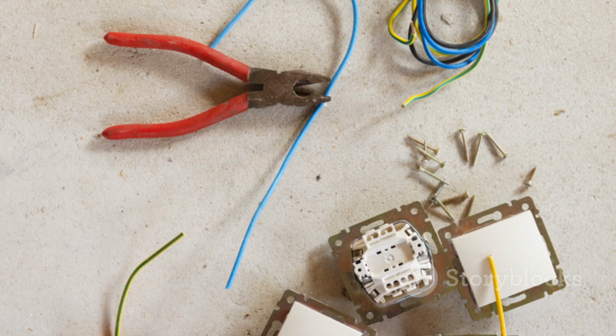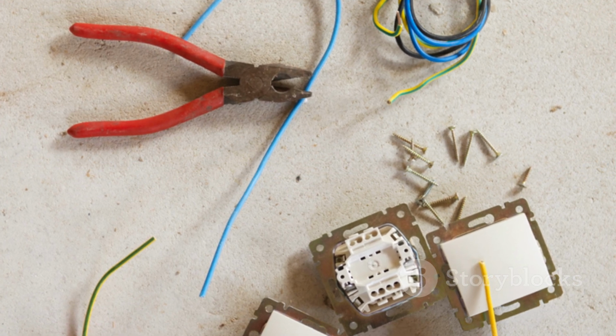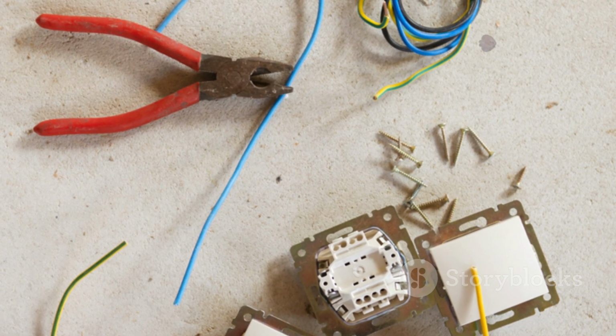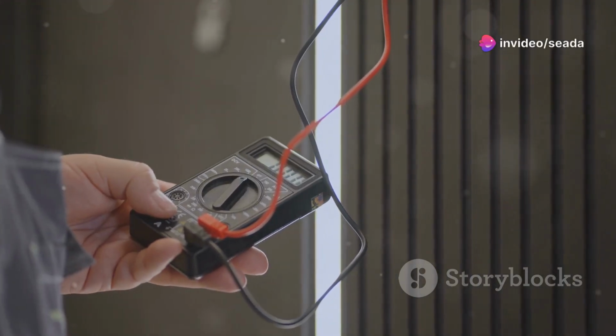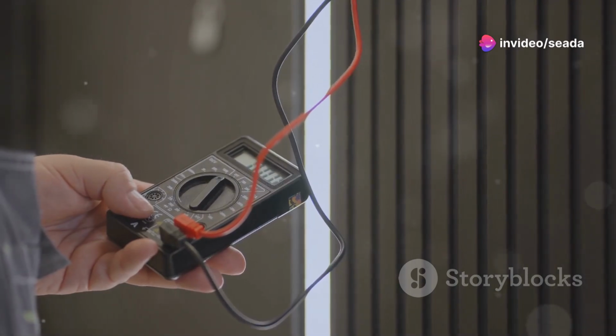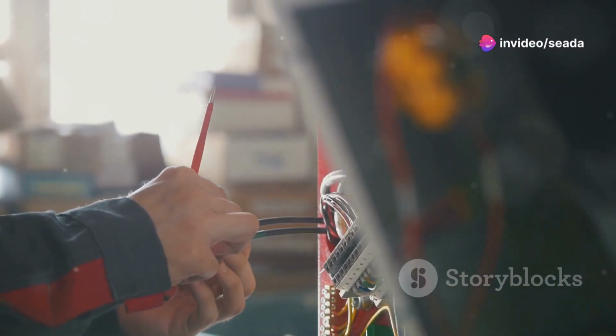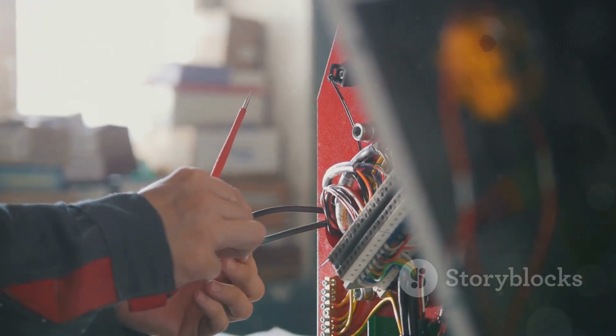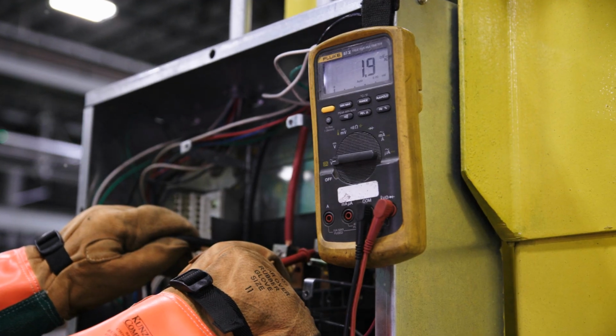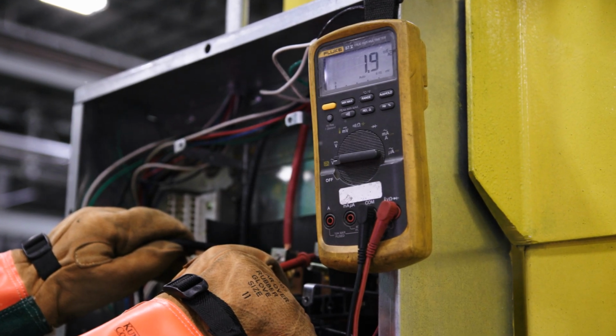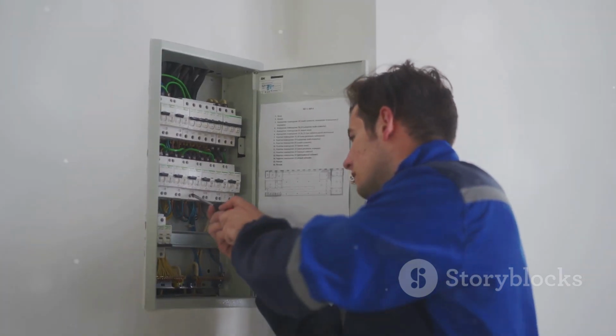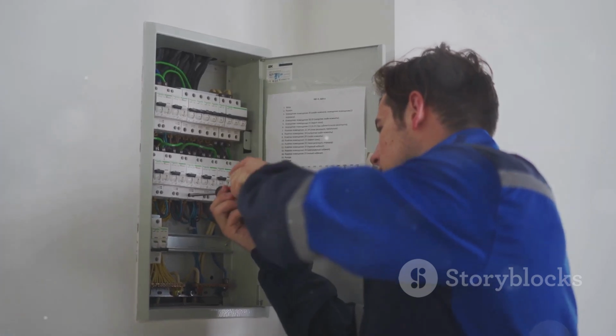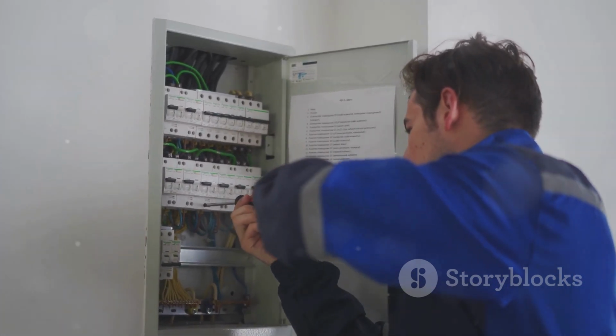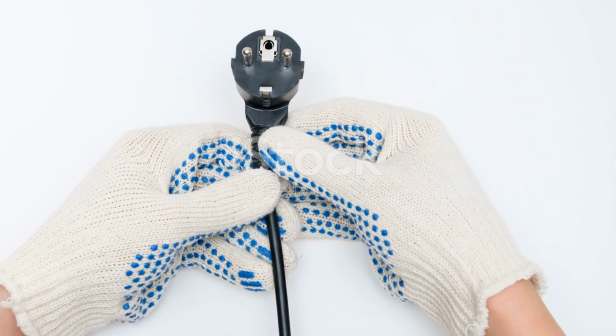Use the right tools, especially insulated screwdrivers and a reliable multimeter. Always isolate, lock out, and test before touching anything. Check connections first. Loose wires are the most common fault. Know your limits. This guide is for basic diagnosis. If the job involves replacing breakers or running new wires, call a licensed electrician. Your safety is the top priority. Make it right every time.